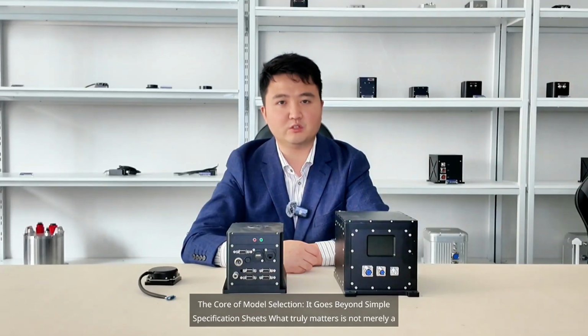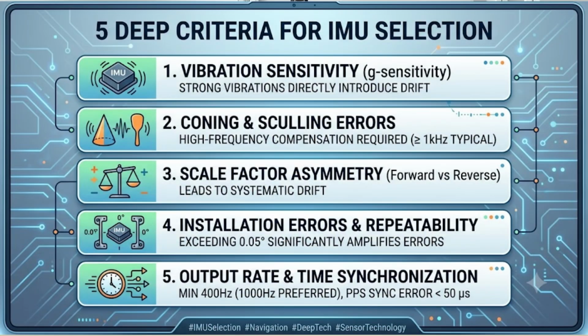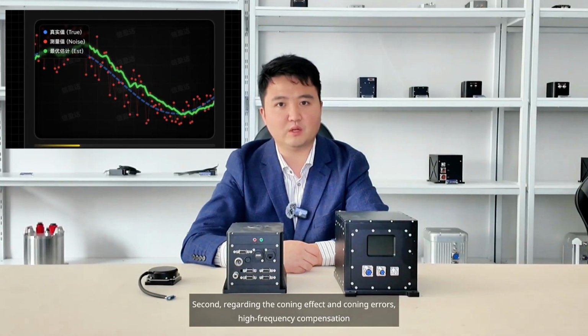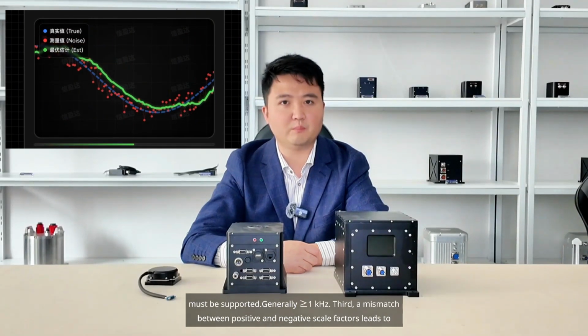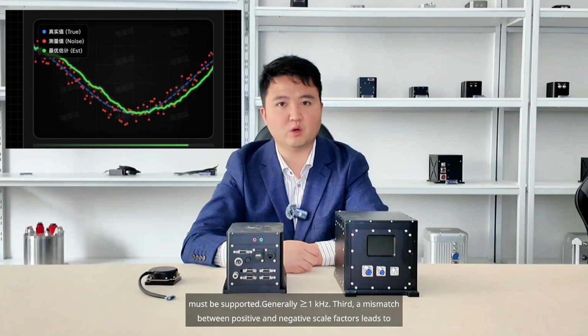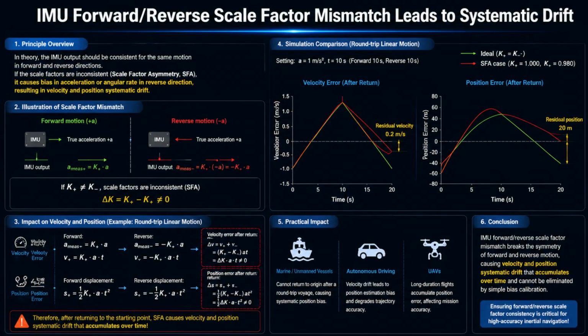The core of model selection goes beyond simple specification sheets. What truly matters is not merely a few basic parameters, but 5 in-depth indicators. First, vibration sensitivity, G sensitivity, directly introduces drift in high vibration environments. Second, regarding the coning effect and coning errors, high frequency compensation must be supported. Third, a mismatch between positive and negative scale factors leads to systematic drift. Fourth, installation errors and repeatability issues exceeding 0.05 degrees significantly amplify errors.